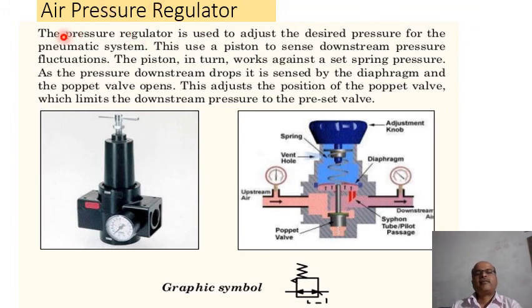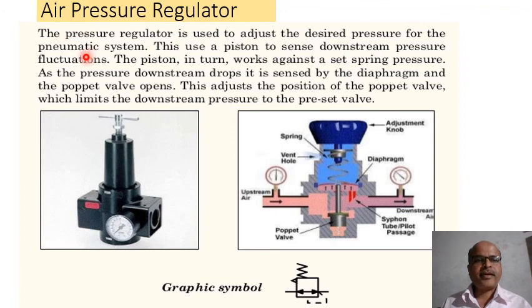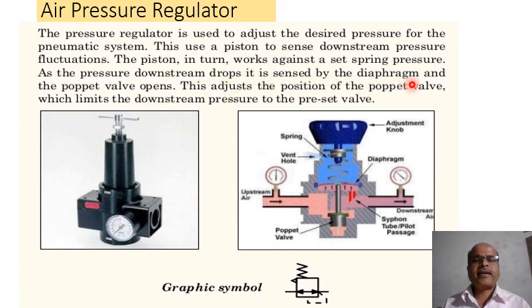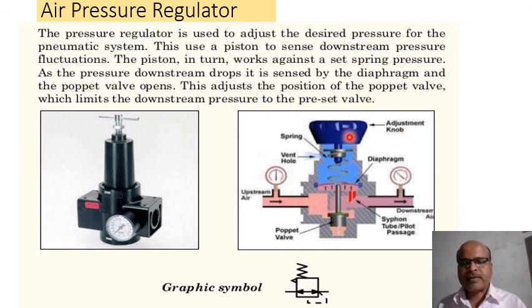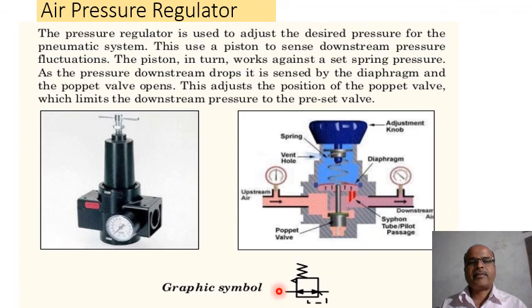The next component is the air pressure regulator. As the name indicates, it regulates the pressure of air. The pressure regulator is used to adjust the desired pressure in the pneumatic system. It uses a piston to sense downstream pressure fluctuations, working against a set spring pressure. As the pressure downstream drops, it is sensed by the diaphragm, which opens the poppet valve, limiting the downstream pressure to the preset value. The adjustment knob, spring, poppet valve, and pilot passage are shown in the diagram, along with the graphical symbol of the air pressure regulator.